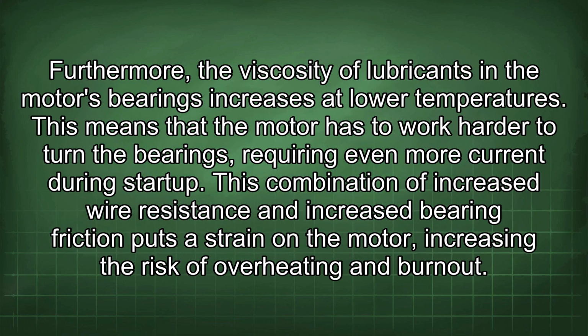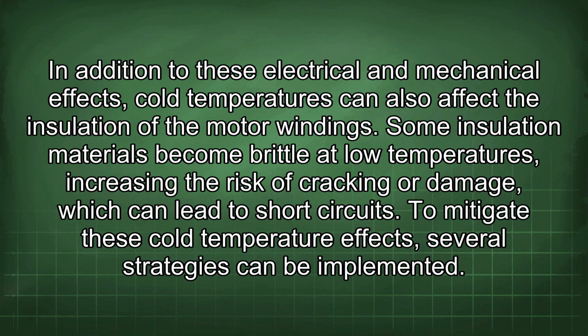Furthermore, the viscosity of lubricants in the motor's bearings increases at lower temperatures. This means that the motor has to work harder to turn the bearings, requiring even more current during startup. This combination of increased wire resistance and increased bearing friction puts a strain on the motor, increasing the risk of overheating and burnout. In addition to these electrical and mechanical effects, cold temperatures can also affect the insulation of the motor windings. Some insulation materials become brittle at low temperatures, increasing the risk of cracking or damage, which can lead to short circuits. To mitigate these cold temperature effects, several strategies can be implemented.